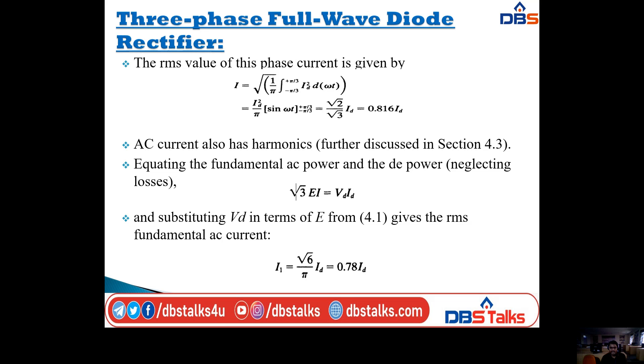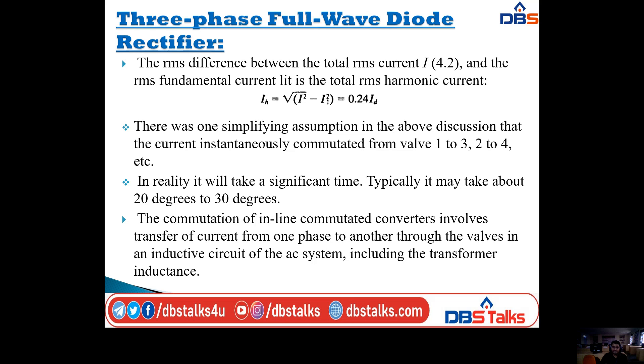The AC current also has harmonics. Equating the fundamental AC power and DC power and neglecting losses: √3 · E · I = Vd · Id. Substituting Vd in terms of E gives the RMS fundamental AC current I₁ = (√6/π) · Id = 0.78 Id. The RMS harmonic current is Ih = √(I² − I₁²) = 0.24 Id.